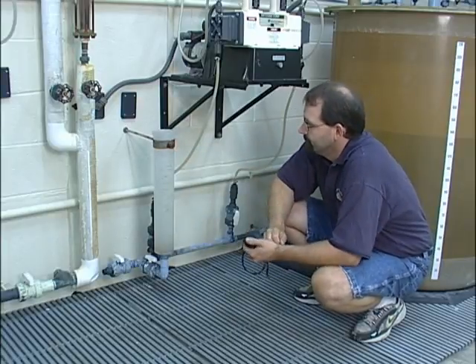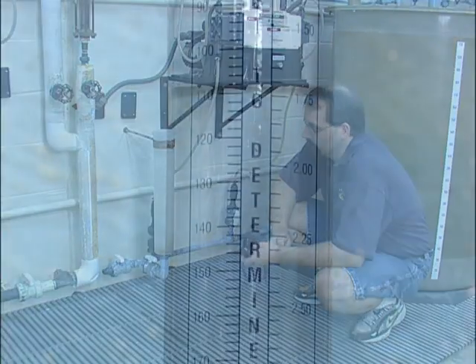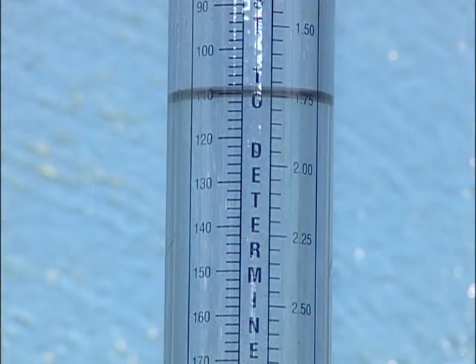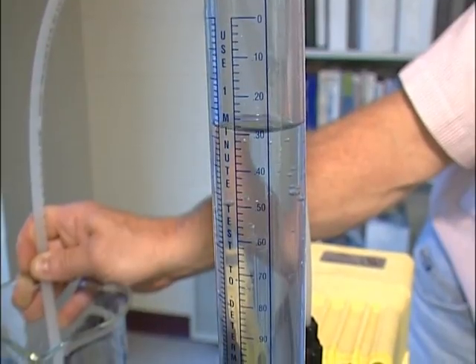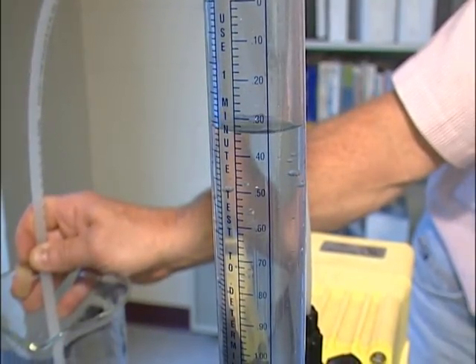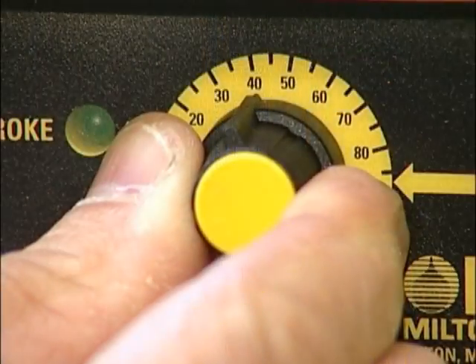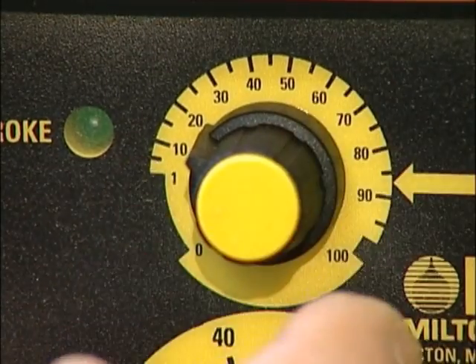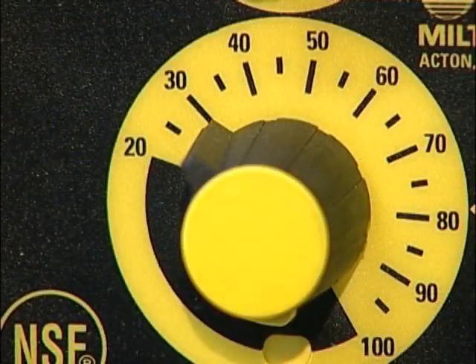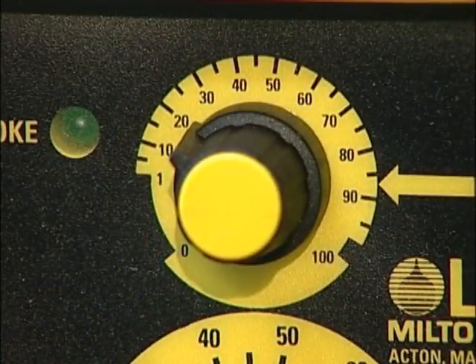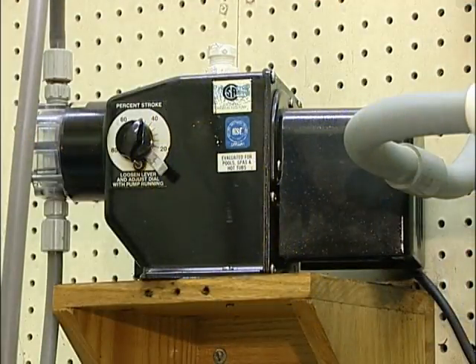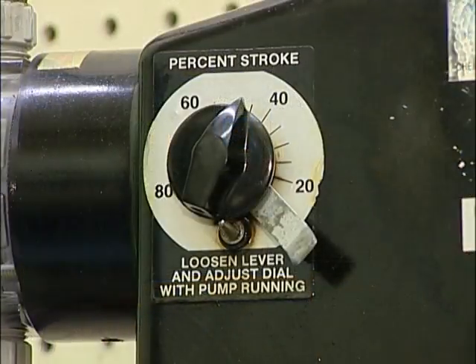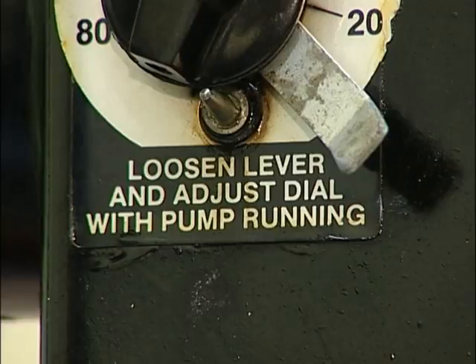Using the actual liquid to be pumped when calibrating is preferable to using water, because different liquids may have different viscosities, which means they may have different delivery characteristics. Prime the pump by turning it on and operating until the chemical is being ejected from the discharge side. Next, set the pump at the lowest setting to be used in the calibration. If the pump has speed and stroke settings, set the stroke to 30 and the speed to 20. Caution should be exercised when adjusting the pump to follow the manufacturer's recommendations for adjusting. Some manufacturers state that adjustments are to be made only when the chemical pump is operating. Otherwise, the pump may be damaged.